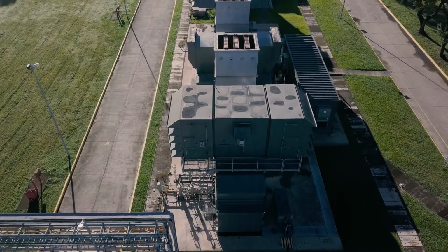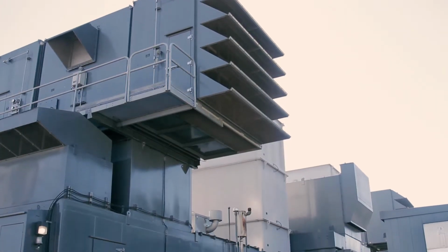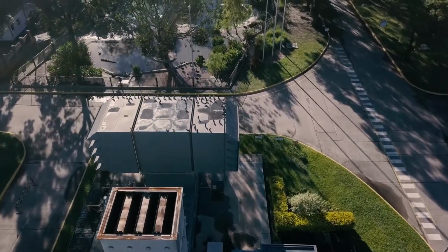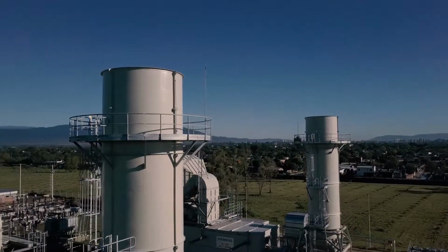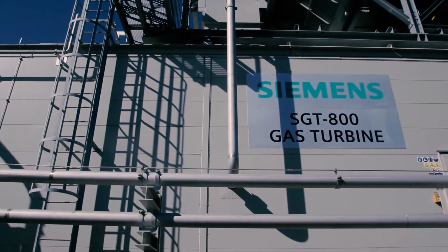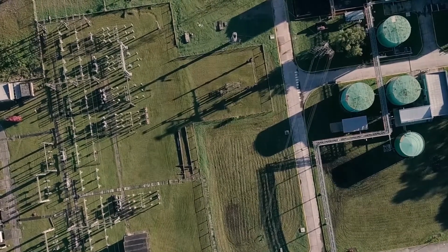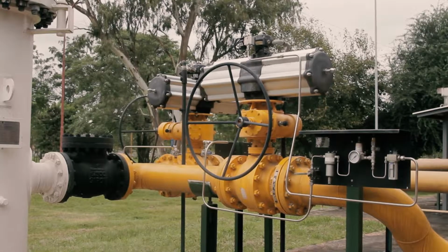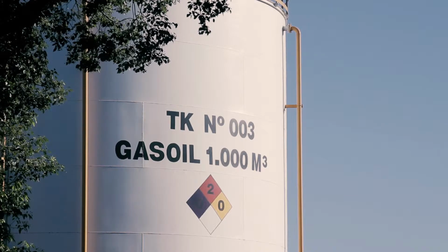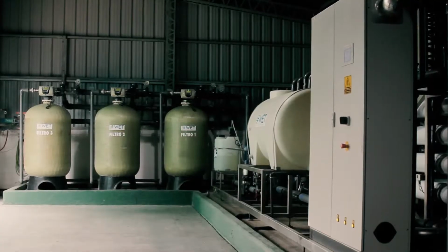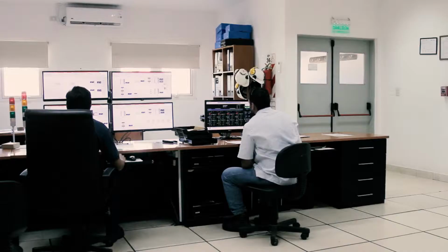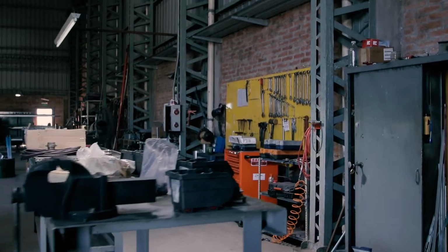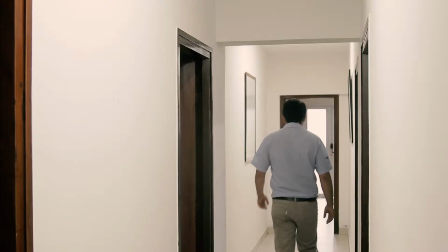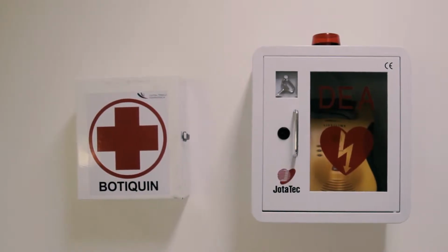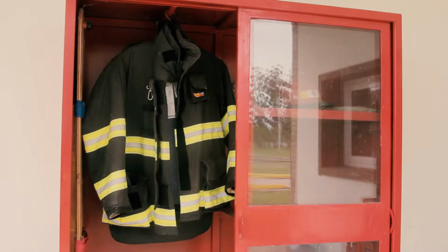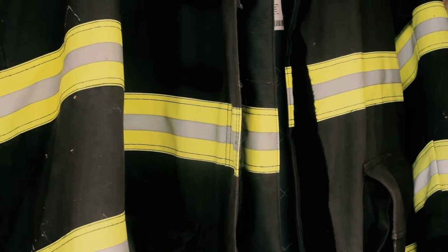This power plant has 4 turbo groups, 2 of 60 megawatts of brand Pratt & Whitney of the aeroderivatives turbines type, and 2 turbo groups of 50 megawatts of powers of Siemens brand of the heavy-duty type. It also has gas fuel feeding system, liquid fuel feeding system, water treatment plant, operation control room, mechanical and electrical maintenance workshops, offices and security guard posts. This plant also has an automatic external defibrillator and firefighter equipment.